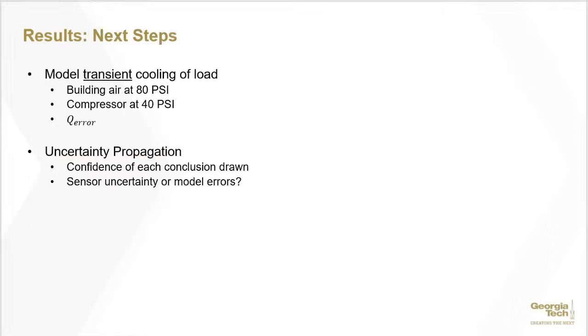The next step in our experimental analysis includes modeling a transient cooling of a load, meaning that it would not be modeled at steady state anymore, both by using building air at 80 psi and by using a compressor at 40 psi, and the predicted energy transfer from theory will be compared with the measured experimental results from these tests to determine how much deviation there is, so the Q error will be found. The uncertainty propagation will also be done to determine the confidence of each conclusion drawn and to determine whether the sensor uncertainty or the errors of the model are causing this uncertainty.